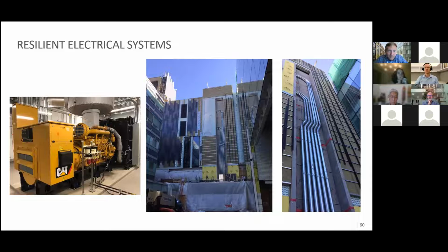So you had to put it up on a fire rated, like a 2, 3, or maybe 4 hour precast concrete chase up the side of the building and into those spaces at level 5 and 6, way up in the air. While the air handling units and the emergency generator were already located in the rooftop penthouse, the fuel oil storage for that generator is still located in the basement.